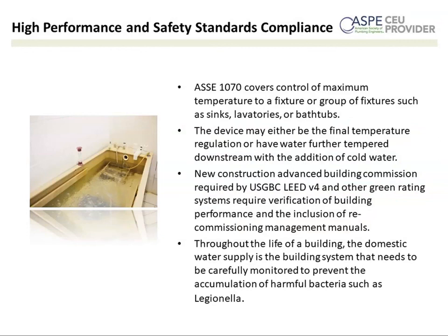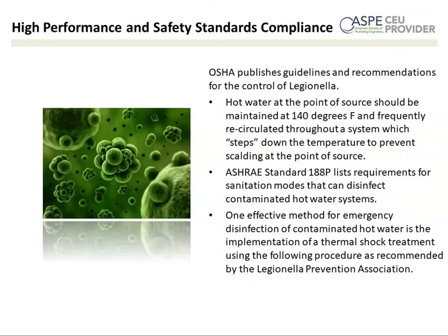So ASSE 1070 is primarily the standard you will see for valves at sinks and laboratories and tubs. These are very, very common. They're all basically type T valves. They're all thermostatic valves. Every manufacturer that does a 1070 valve makes a thermostatic valve. Most of them use paraffin actuation. And at 1070, the device can be either the final temperature regulation device, or the water can be tempered further downstream. So I would say 1016 and 1070 are the two most common types of valves.